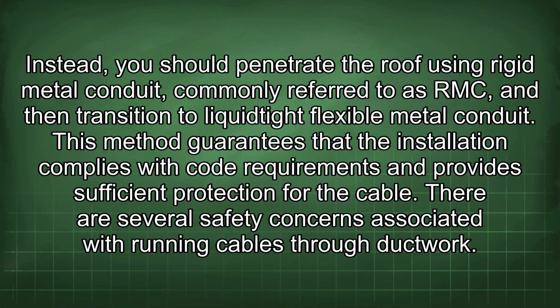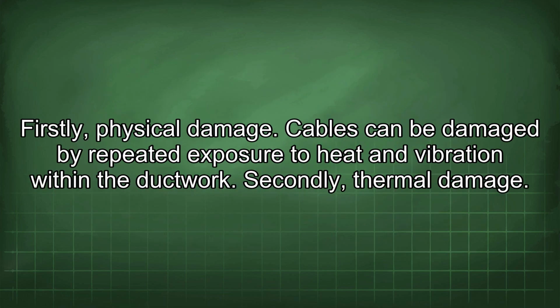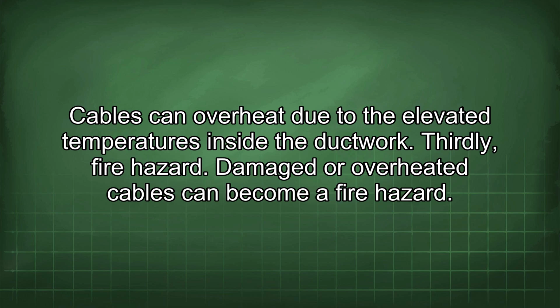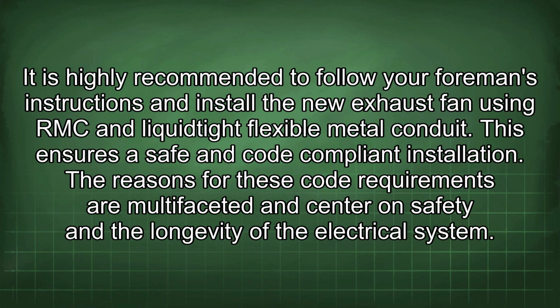There are several safety concerns associated with running cables through ductwork. Firstly, physical damage. Cables can be damaged by repeated exposure to heat and vibration within the ductwork. Secondly, thermal damage. Cables can overheat due to the elevated temperatures inside the ductwork. Thirdly, fire hazard. Damaged or overheated cables can become a fire hazard. It is highly recommended to follow your foreman's instructions and install the new exhaust fan using RMC and liquidtight flexible metal conduit. This ensures a safe and code-compliant installation.